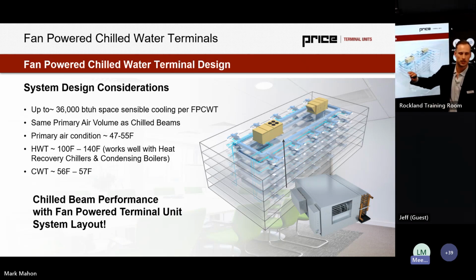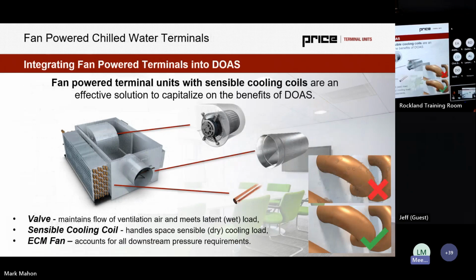We're seeing it work with the same system designs. So when we look at heat recovery chillers, when we look at incorporating air source heat pumps, when we look at condensing boilers, it slots in the same way with the same rationale as a chilled beam system. And we're still looking at that elevated chilled water temperature of 56 or 57 degrees Fahrenheit, which is going to make sure this large coil on the return of the unit stays dry and does not condense.